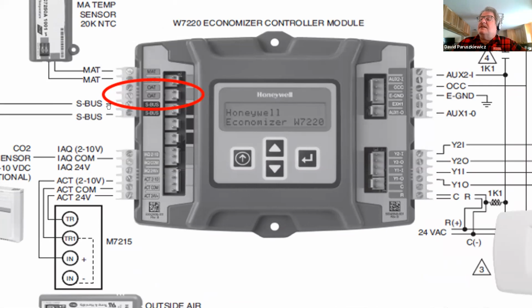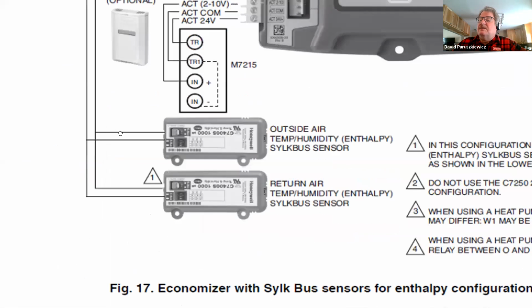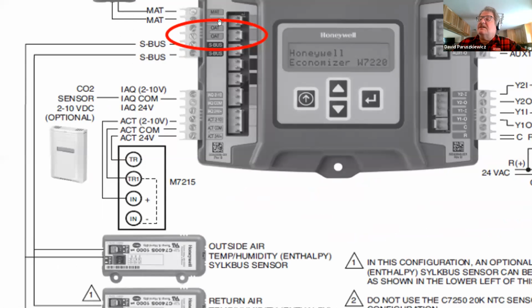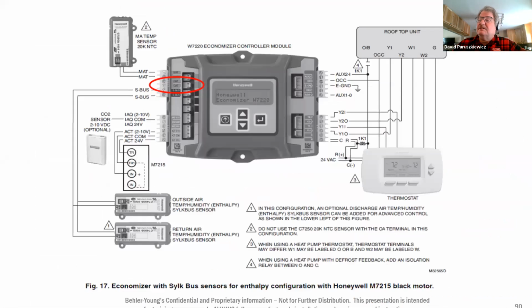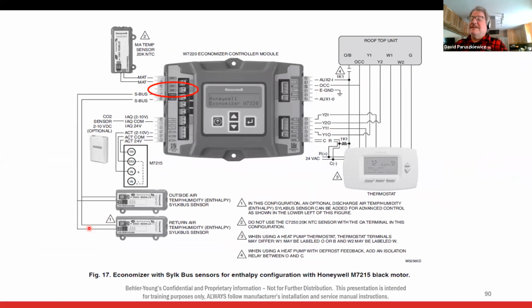But what guys see is they install one of these and say, well, I don't have an outdoor air temperature sensor. So they take the wires off of here and connect it here, and then they call me because they're getting a fault. All right. So the enthalpy sensors are tied in to the S bus, not the outdoor air temperature sensors. Okay, and then there's a mixed air sensor, which is MAT. And then aux2, I want to talk about this for a minute.